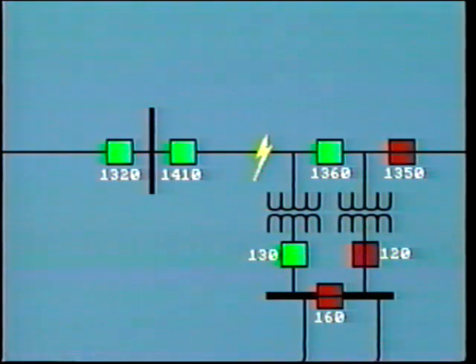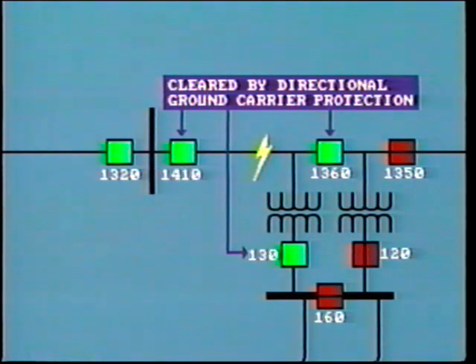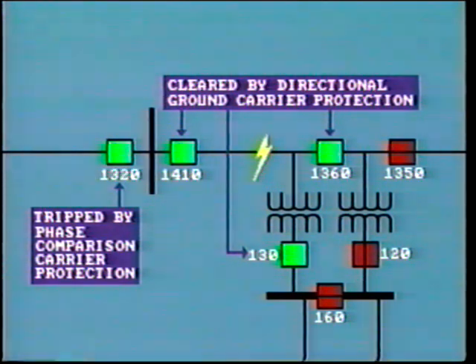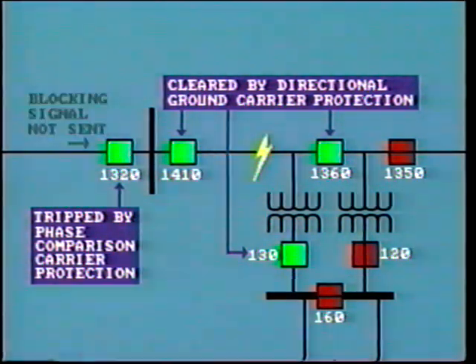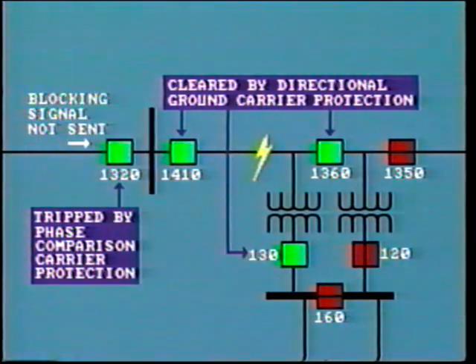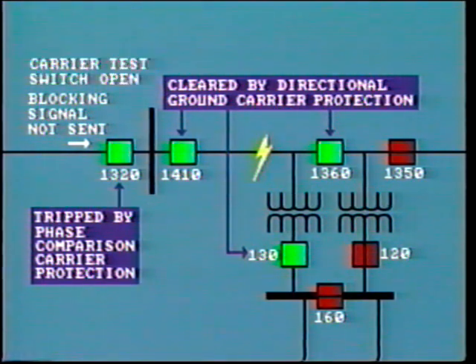Another case of a trouble call is shown here. The task was to discover why breaker 1320 tripped for a fault on the other line. In fact, the faulted line cleared correctly. Both breakers opened, as well as the breaker on the transformer tap. These were cleared by directional ground carrier protection. However, breaker 1320 should not have operated for a fault outside of its zone. This breaker was tripped by phase comparison carrier protection. The investigation showed that the blocking signal was not sent from the other end of the line, and the reason for this was that the test switch had not been properly reset to the on position, presumably since last testing. In this case, in order to avoid a repeat, the test switch contact was removed from both ends of the line.